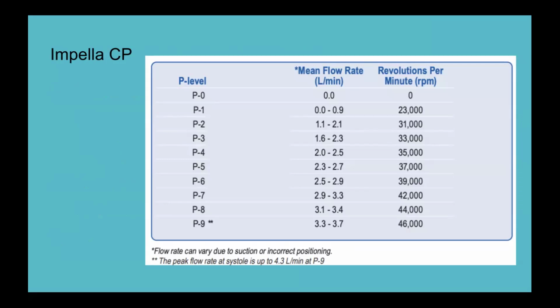Because it's preload dependent and afterload sensitive, you're not actually choosing flow. You're choosing a P level. A P level is the performance level. It corresponds to the revolutions per minute that the device is spinning at. And then based on preload conditions and afterload conditions, you get an approximate flow. But again, you're setting a P level, which is really setting RPMs.